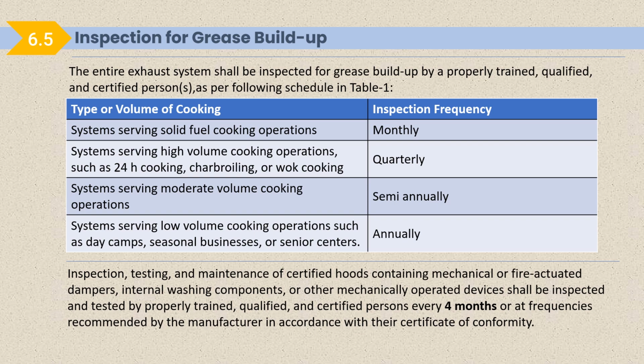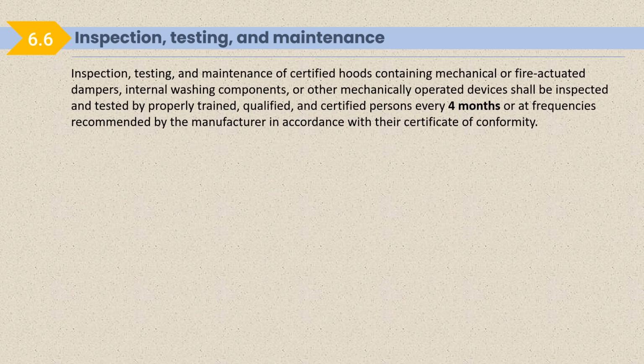Inspection, testing and maintenance of certified hood containing mechanical or fire actuated dampers, internal washing components or other mechanically operated devices shall be inspected and tested by properly trained, qualified and certified persons every 4 months or at the frequency recommended by the manufacturer in accordance with their certificate of conformity.